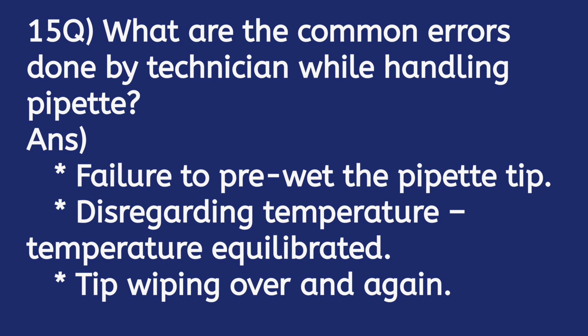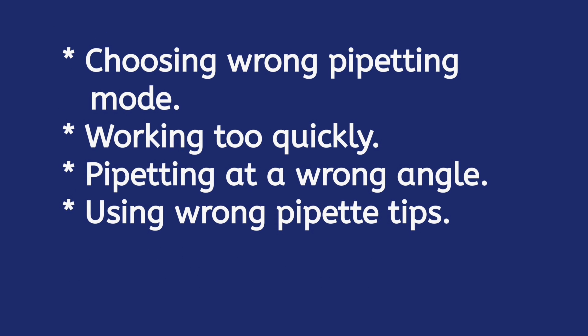What are the common errors made by technicians while handling a pipette? Common errors include failure to pre-wet the pipette tip, disregarding temperature equilibration, excessive tip wiping, choosing the wrong pipetting mode, working too quickly, pipetting at a wrong angle, and using wrong pipette tips.